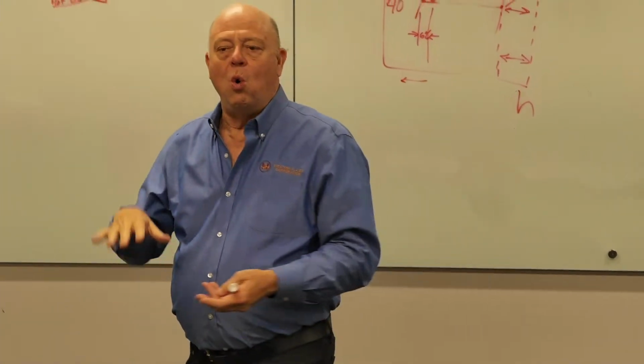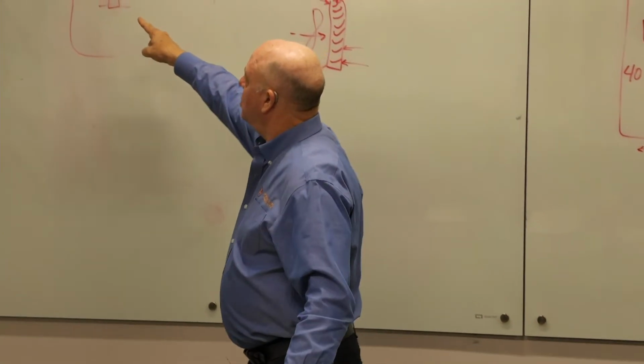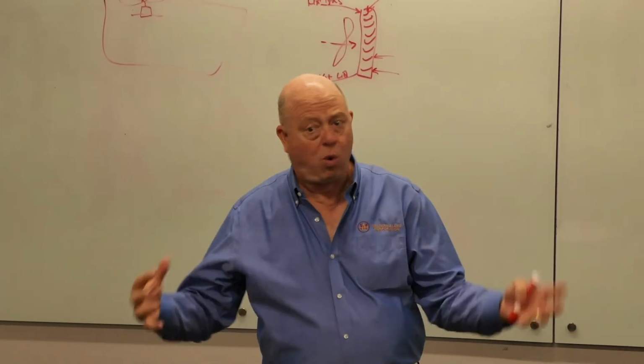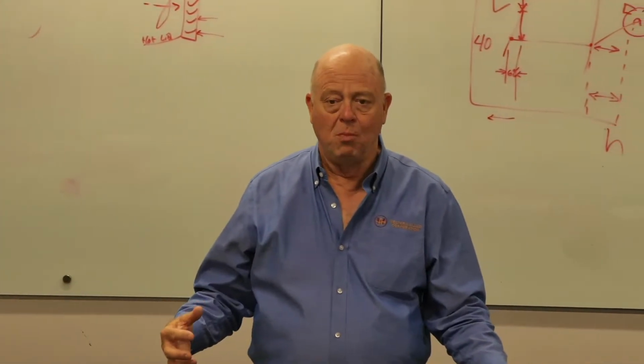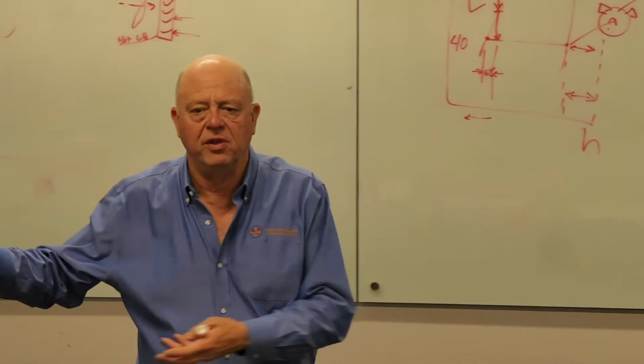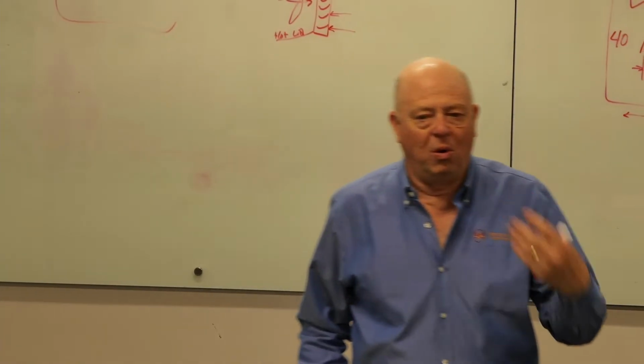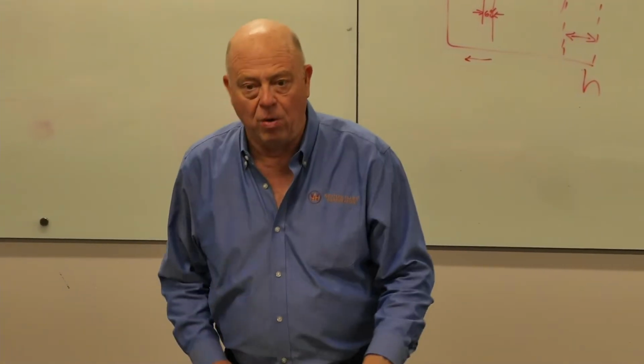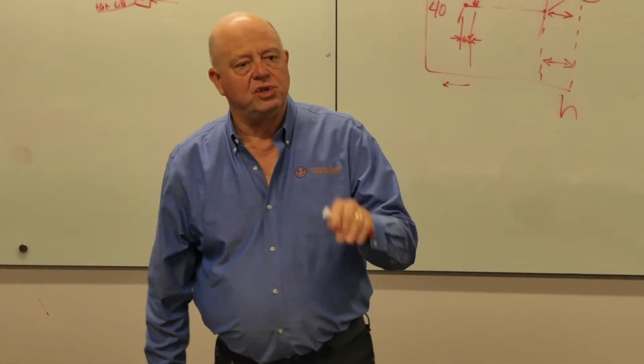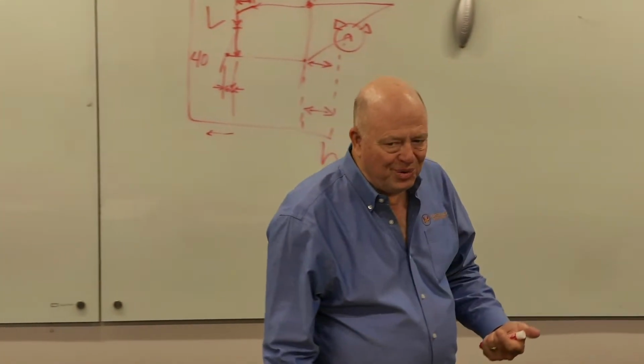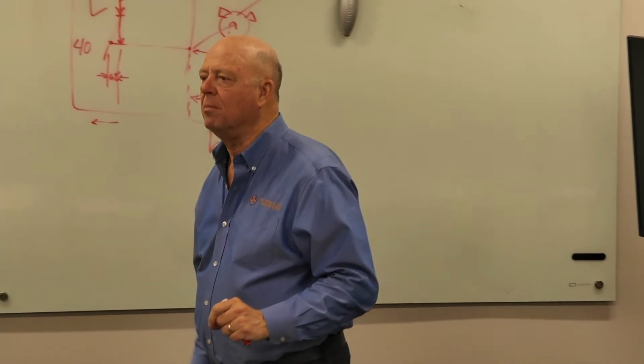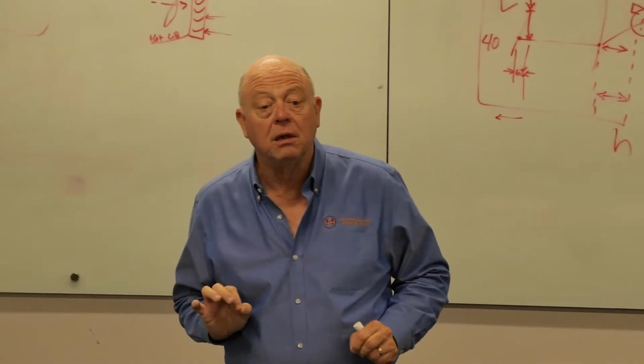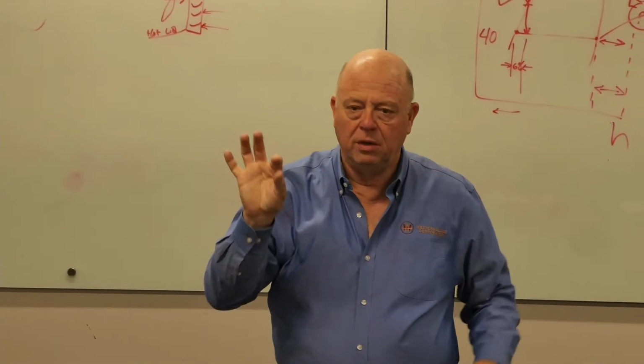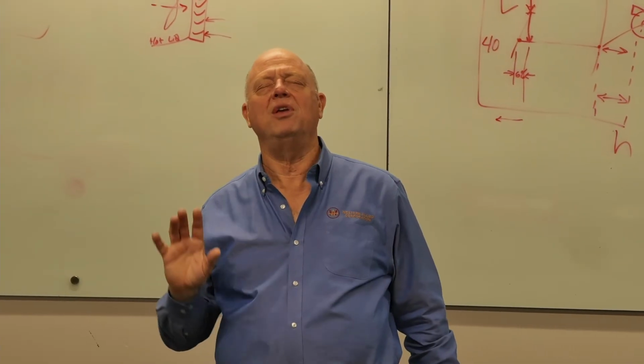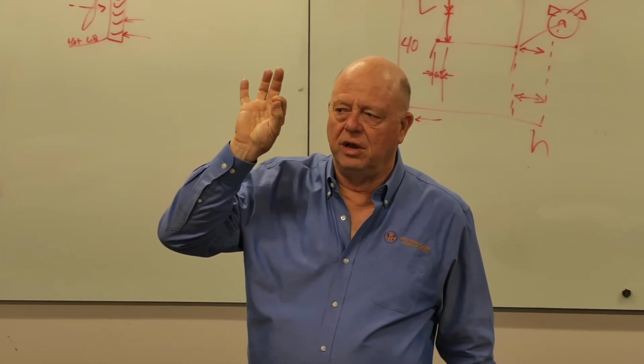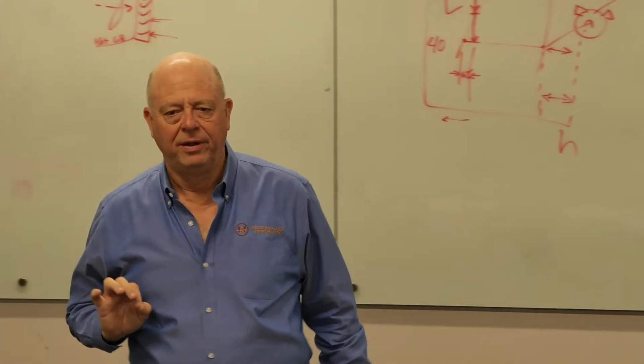And so below, let's say we were trying to run this thing at a quarter speed. We're not at a quarter of the friction. We're, I don't know, 40, 50% of the friction. But where are we at on the torque? Way down. It's not linear. So, Carrier had to add a feature, and they had done that just before I went to work for them. There was a minimum speed setting. Motor couldn't go below, I think back then you had a choice of 40 or 50%. Couldn't go below that.